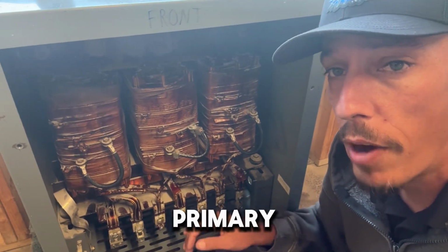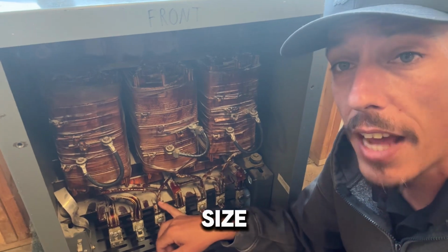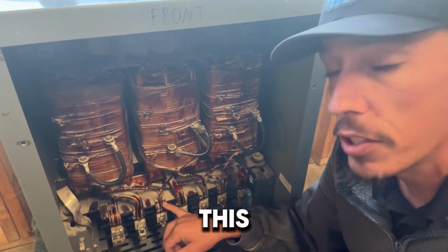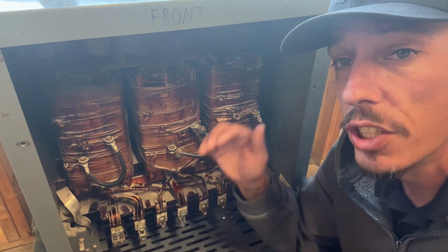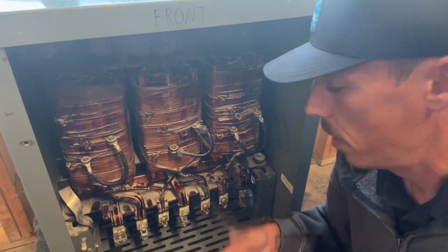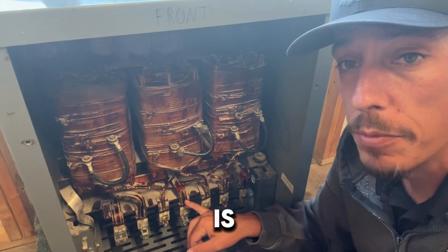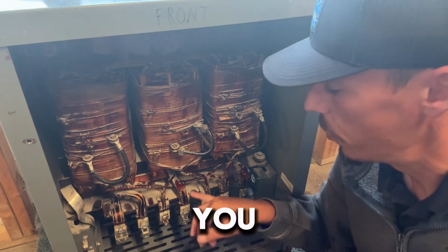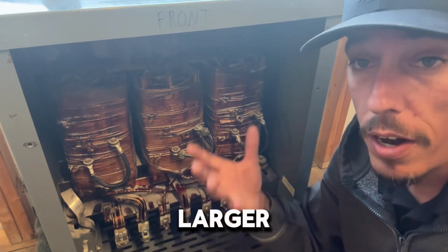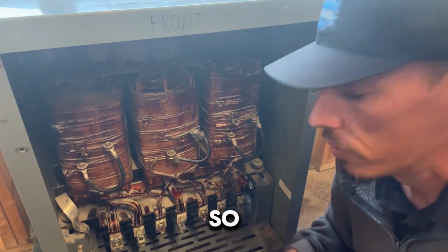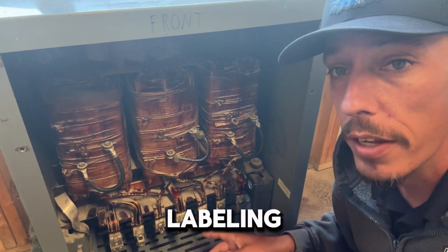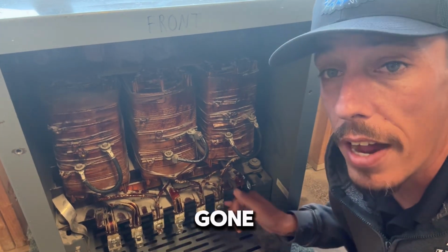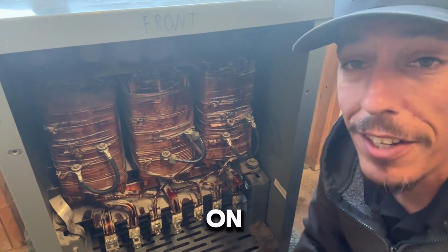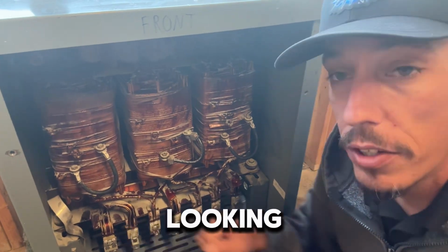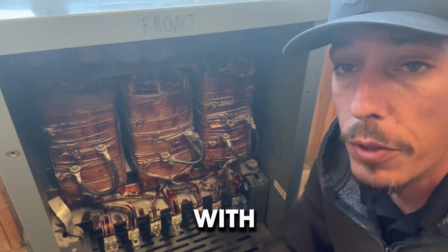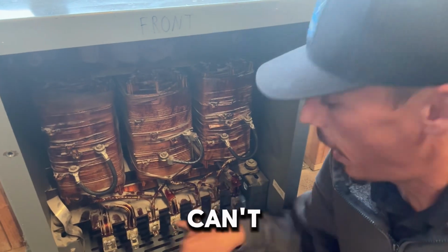You can tell the difference between the primary and secondary just based off the size of the conductor. So we know that this small one is a primary because the voltage is high, but the amperage is low. Whereas on the opposite, the secondary is much thicker of a conductor, so you can tell that it's larger and more amperage, less voltage. So you don't even have to understand or know the labeling, right? Like this one, all the labeling is gone, more or less. I just put some stickers on there. But you can still tell just by looking at the windings. You can also tone it out with your multimeter if you can't tell by the windings.